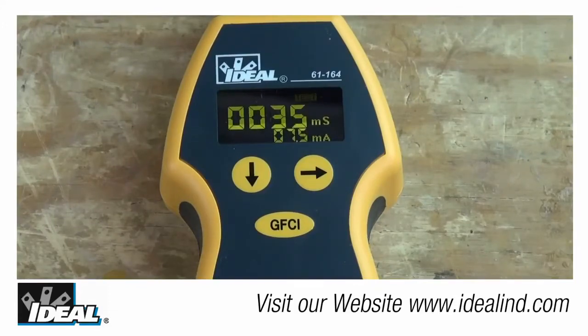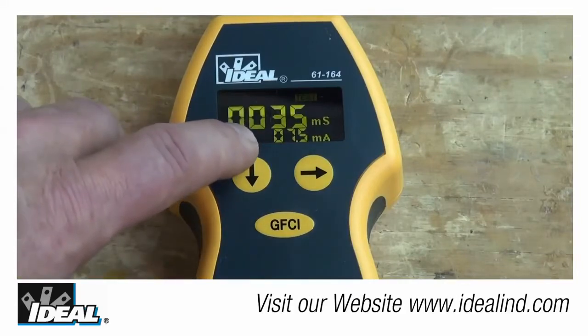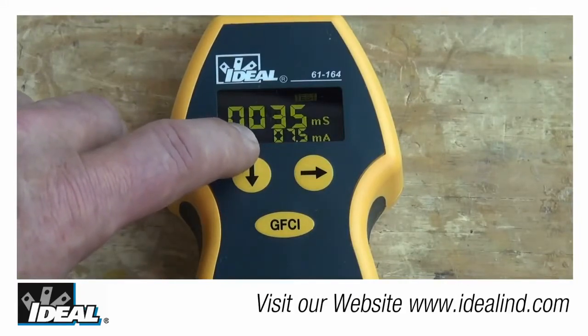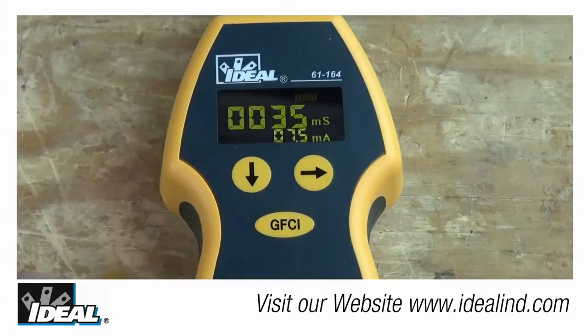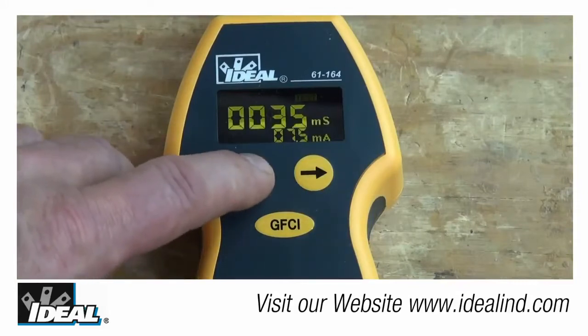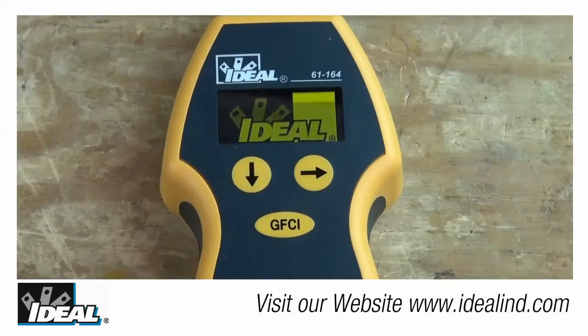Now, the GFCI device should trip within the UL established guidelines, causing the display to blank out with that loss of power. Now, when the GFCI device is reset, the unit's going to display the actual trip time that the GFCI took to respond to that current imbalance and then to open the circuit. And pressing the down arrow button once returns the tester to its wiring verification mode.